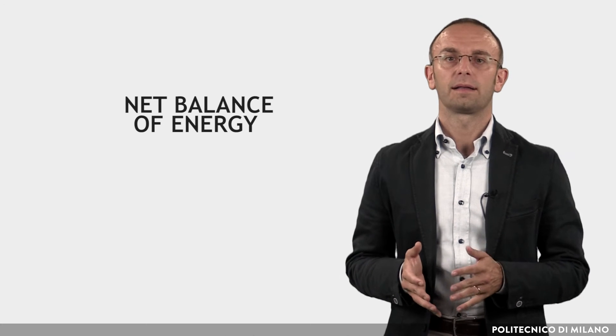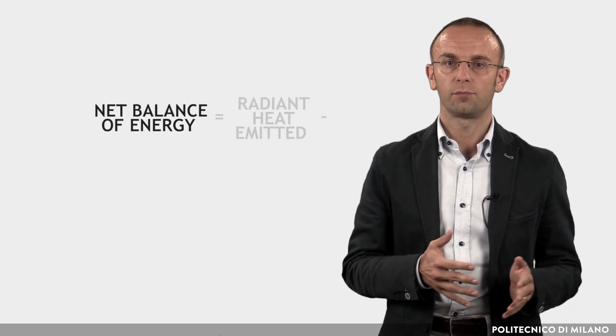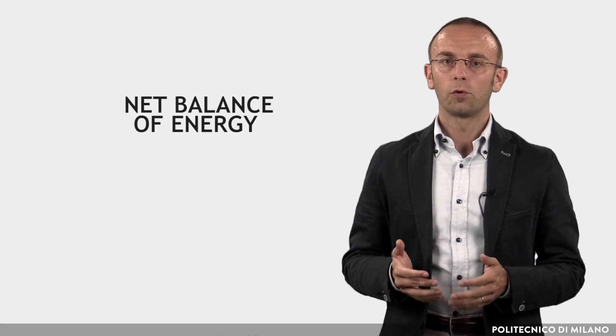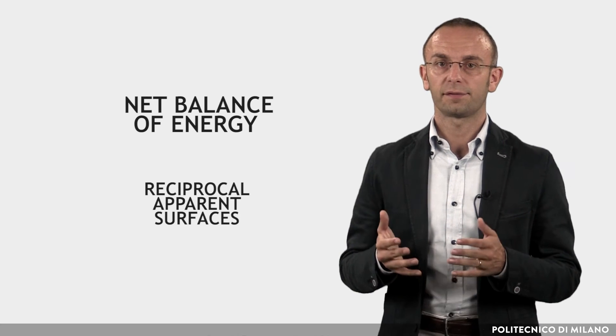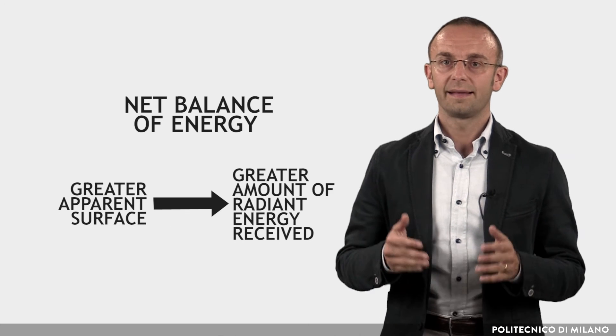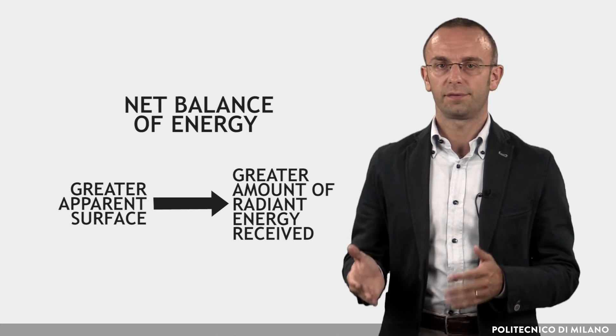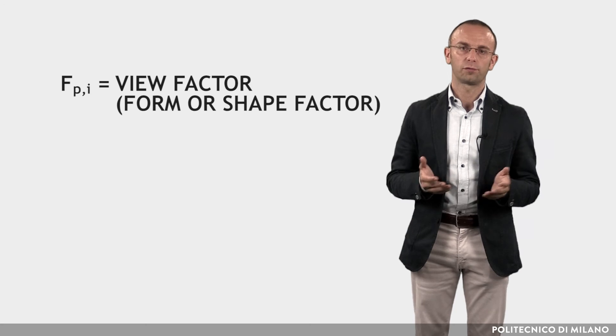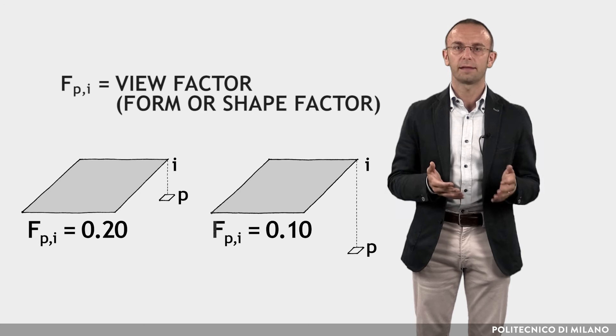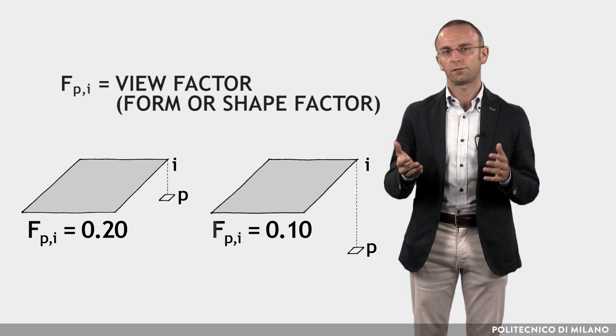An object not only emits but also receives radiant heat, being surrounded by other bodies. What matters is the net balance of energy, which is the difference between the radiant heat emitted and the radiant heat received. This balance depends also on the positions of the bodies, which determine the reciprocal apparent surfaces. The greater the apparent surface, the greater the amount of radiant energy the body receives. To quantify the phenomenon, the view factor Fpi, also called form or shape factor, is used, indicating the proportion of the radiation which leaves a person P that strikes a surface I.